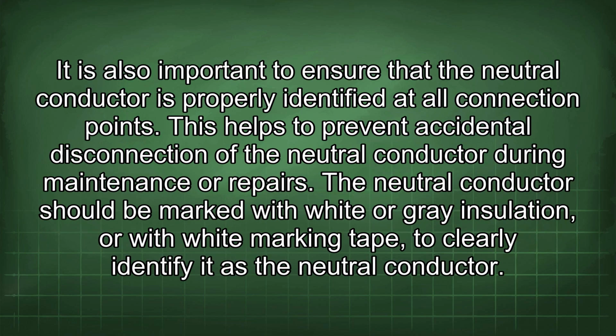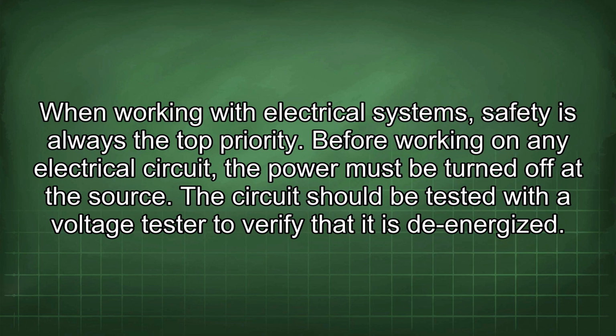It is also important to ensure that the neutral conductor is properly identified at all connection points. This helps to prevent accidental disconnection of the neutral conductor during maintenance or repairs. The neutral conductor should be marked with white or grey insulation or with white marking tape to clearly identify it as the neutral conductor. When working with electrical systems, safety is always the top priority.